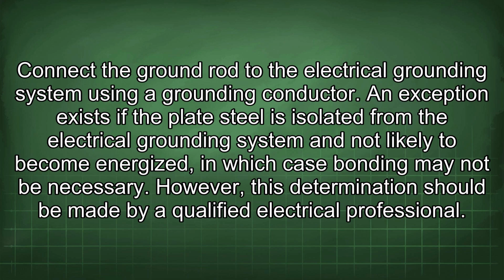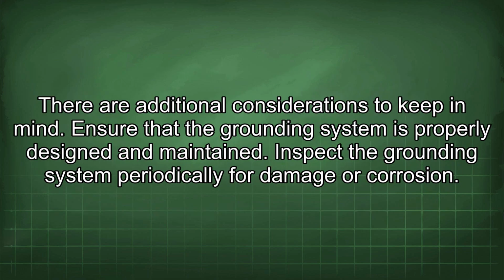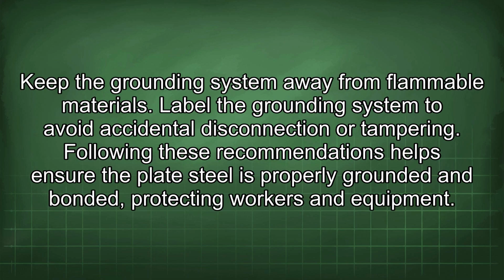An exception exists if the plate steel is isolated from the electrical grounding system and not likely to become energized, in which case bonding may not be necessary. However, this determination should be made by a qualified electrical professional. There are additional considerations to keep in mind. Ensure that the grounding system is properly designed and maintained. Inspect the grounding system periodically for damage or corrosion. Keep the grounding system away from flammable materials. Label the grounding system to avoid accidental disconnection or tampering. Following these recommendations helps ensure the plate steel is properly grounded and bonded, protecting workers and equipment.